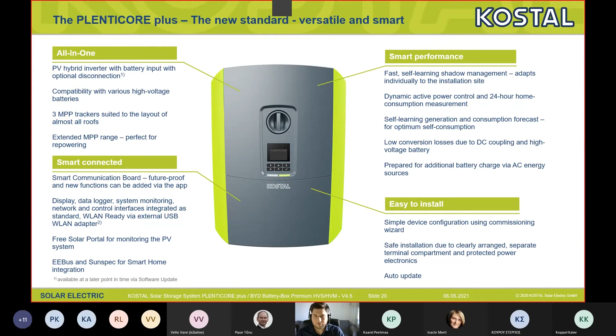And this is the shadow management. I'm really happy about this feature because we have seen real smiles from our installers. In cases where we have partial shadows on a PV string from tall trees, antennas, chimneys, whatever, you can activate this shadow management. It's an improvement in the algorithm of the MPPT tracker. The shadow management can predict, because the inverter keeps historical data, the time we will have shadow, and can adjust more quickly and efficiently the maximum power point on the IV curve. So at the end of the day we could have up to 30% more yield compared to a partially shadowed PV system without this feature.